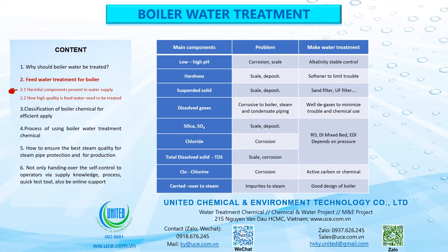5. Main component: Silica, SO4. Problem: scale and deposit. Water treatment should include RO or DI mixed bed, depending on pressure. 6. Main component: Chloride. Problem: corrosion. Water treatment should include RO or DI mixed bed, depending on pressure. 7. Main component: Total dissolved solids (TDS). Problem: scale and corrosion. Water treatment should include RO or DI mixed bed, depending on pressure.